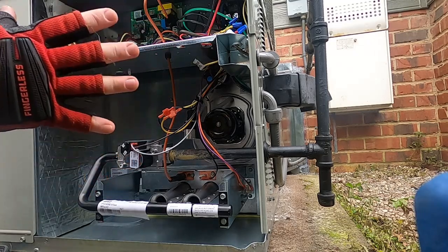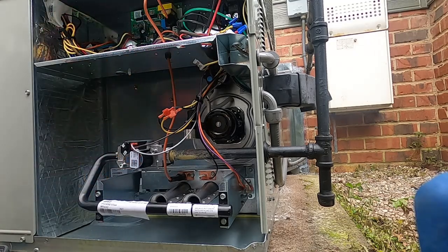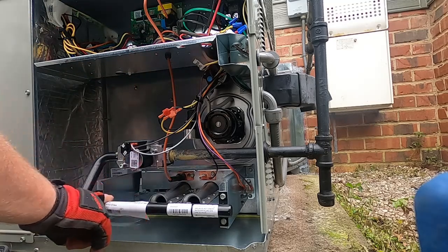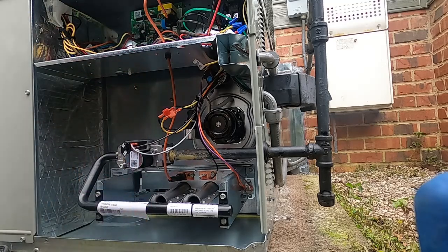This is a single stage gas package unit, and for whatever reason, in a situation like this, we've got that paperwork we have to fill out, kind of a commissioning form. Some of the numbers, I just kind of know what they are. They're kind of fixed, but basically we need to check the operations on it, make sure the gas pressure is set right, inlet pressure is correct, run it, set superheat, subcooling, temperature rise, temperature split, static airflow on it, all those good things. And you've got to fill out that paperwork and then turn it in with everything else. It's just part of what they want us to do.